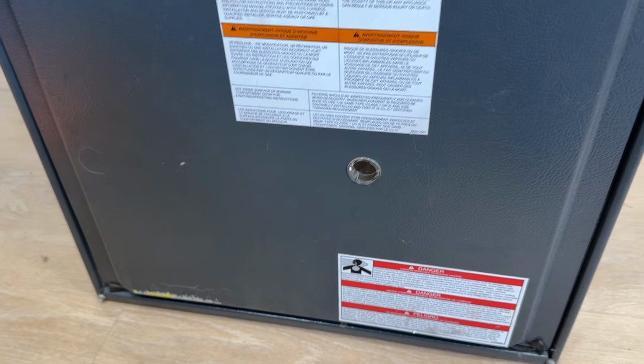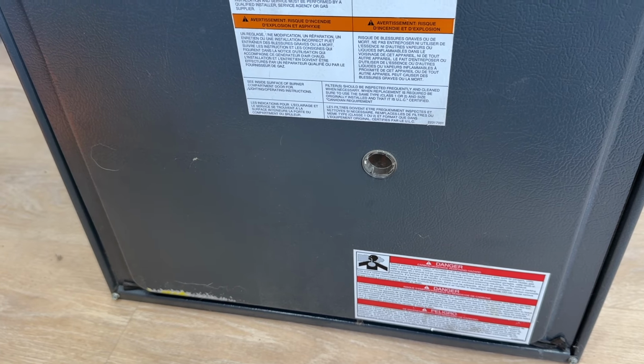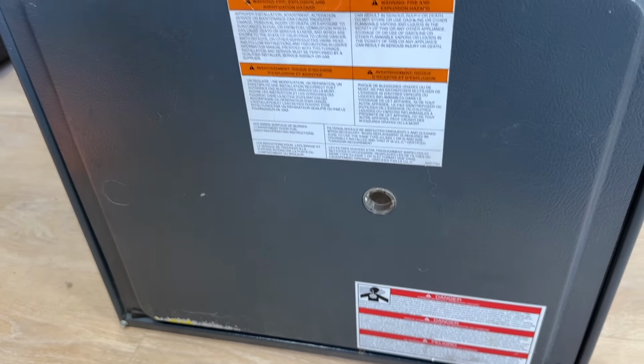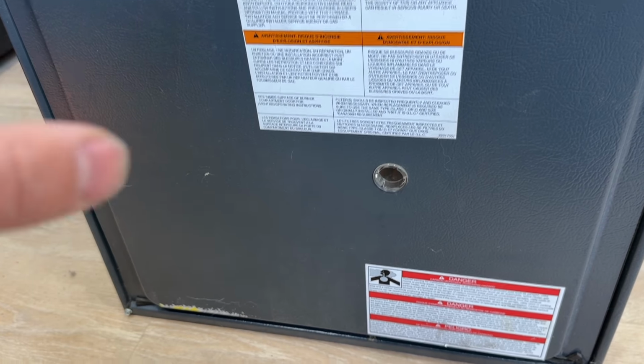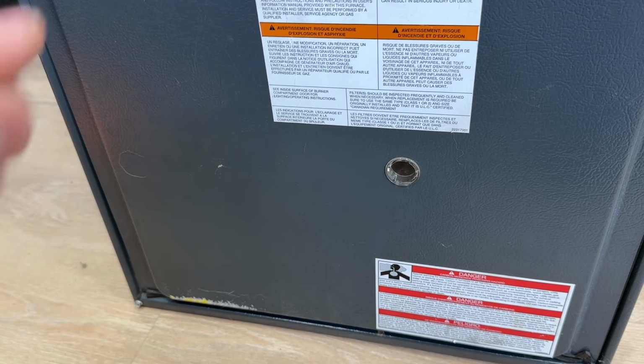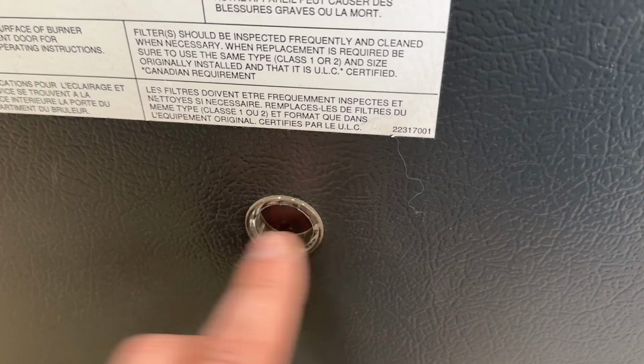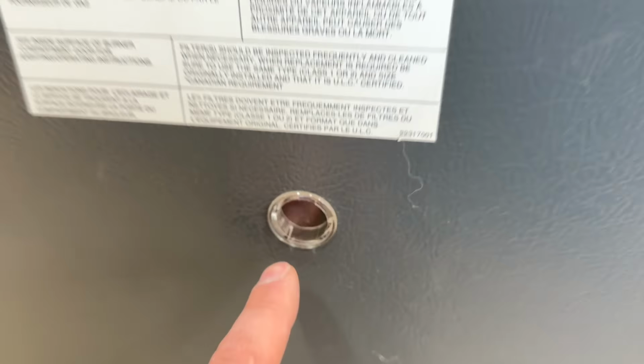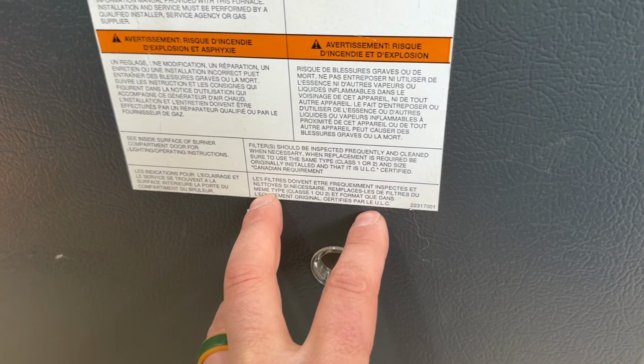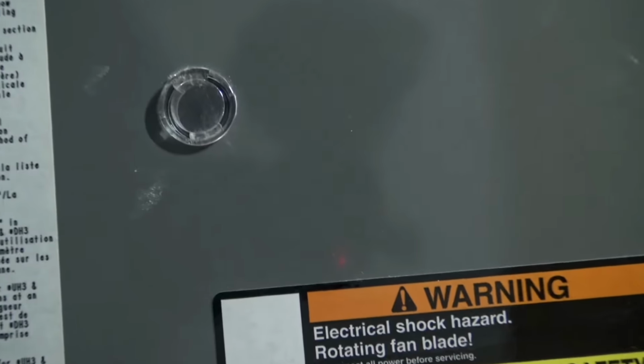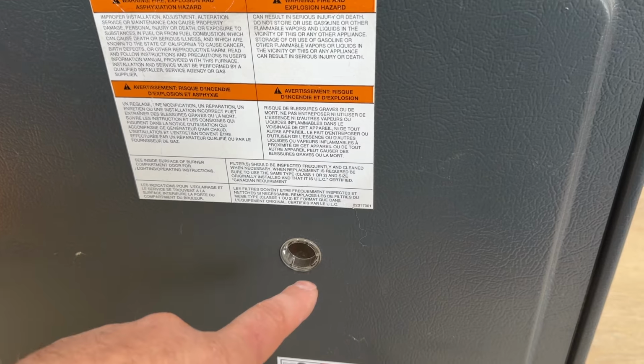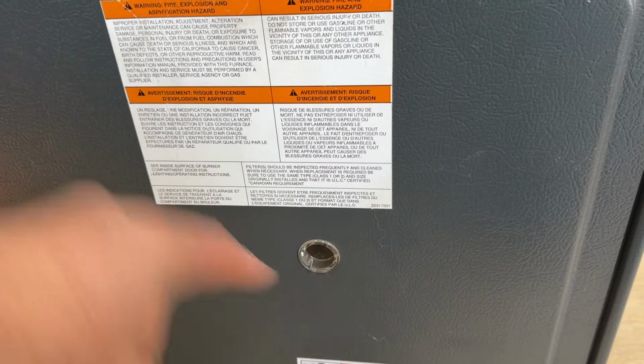Okay, so before we get into these 5 tips, I want to just show you something that's critically important. If your furnace is not working, before you try and reset it, turning the switch off and then back on, make note of this little sight glass and look inside of here and see if you can see what code is flashing, because as soon as you reset the furnace, this code will erase itself. So you want to check this very first before you do anything else, and a lot of times that will give you an indication as to what's going on with your furnace.